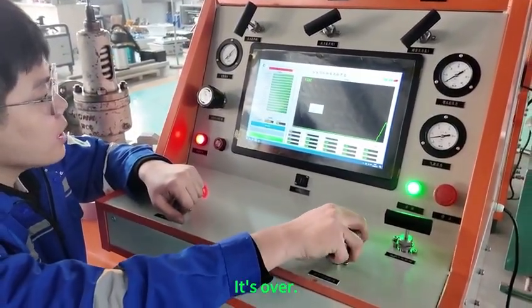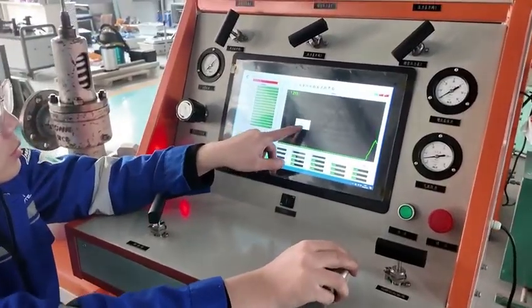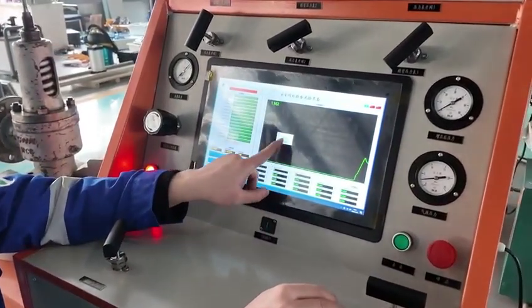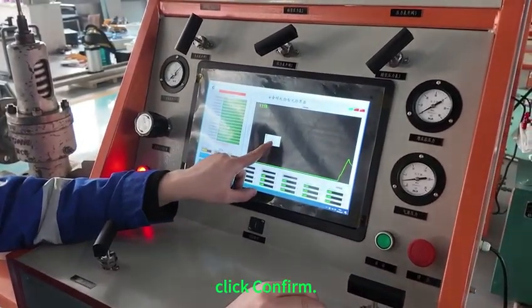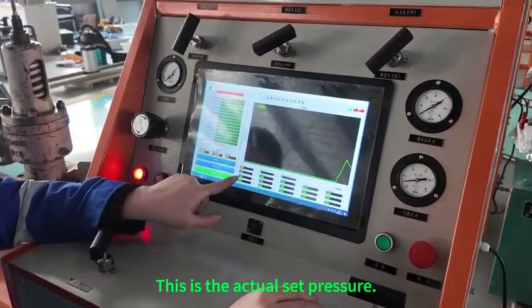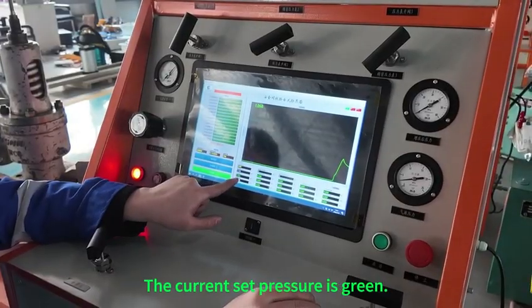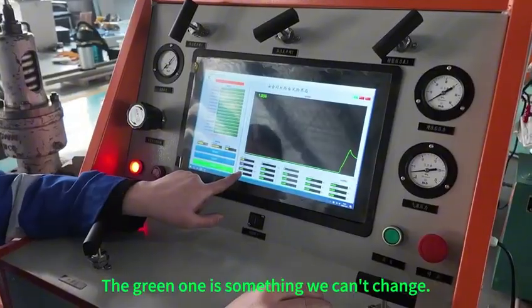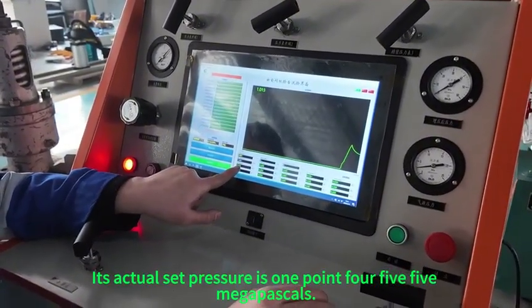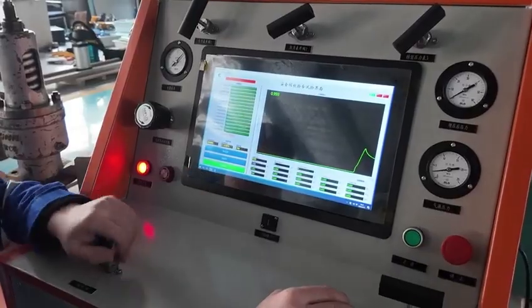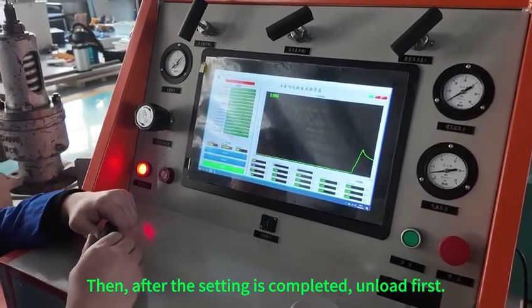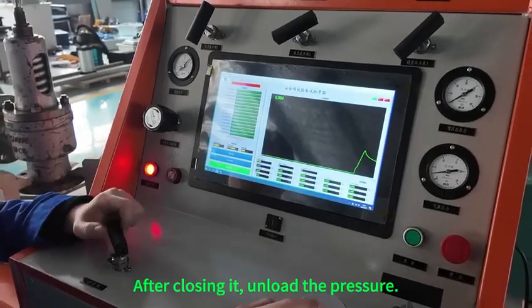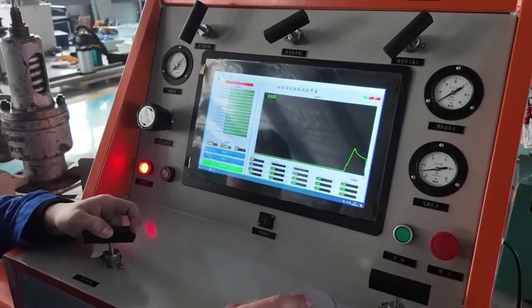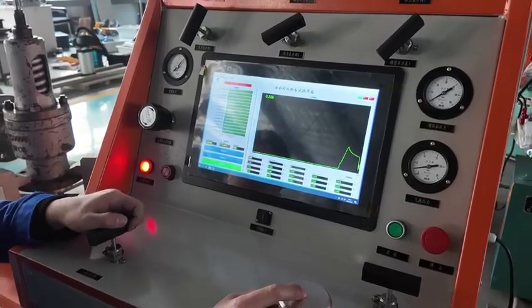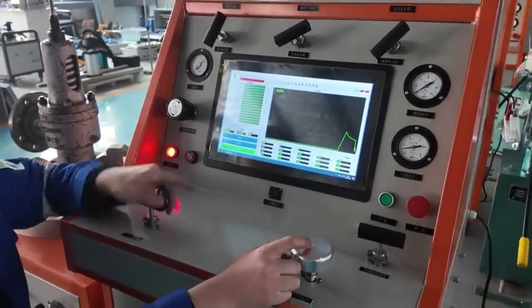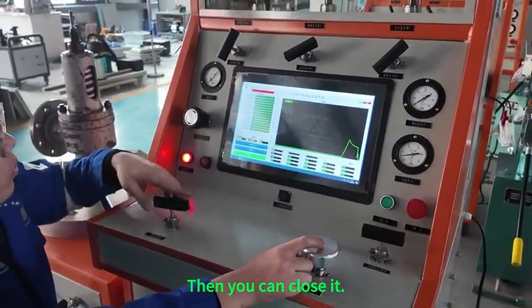Okay. It's over. Click confirm. This is the actual set pressure. The current set pressure is shown in green, and the green one is something we can't change. Its actual set pressure is 1.455 megapascals. Then, after the setting is completed, unload first. After closing it, unload the pressure. Okay. When the pressure gauge is almost zero, then you can close it.